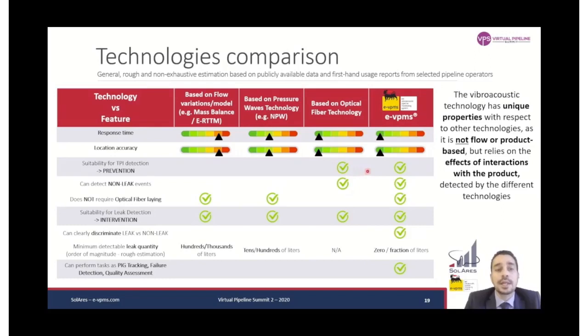It makes a good technology for prevention, not just intervention, because it can detect no-leak events. One major difference with optical fiber is that EVPMS does not require optical fiber laying. This is maybe the most important point to notice about EVPMS: it can clearly discriminate what is a leak from what is not, and the minimum detectable leak quantity is almost zero, fractions of liters. As far as we currently know, it is the only detection system capable of performing tasks like PIG tracking, failure detection, quality assessment, and all that you saw in this presentation.